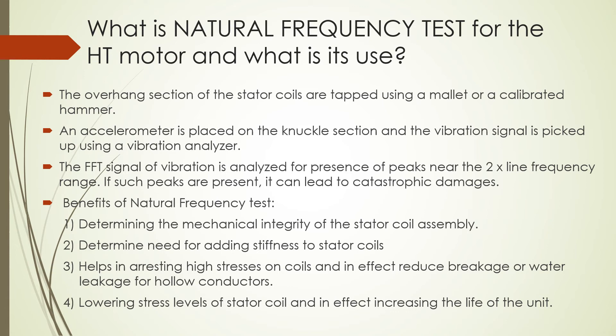The eighth question: what is the natural frequency test for an HT motor and what is its use? The overhang section of the stator coil is tapped using a mallet or calibrated hammer. An accelerometer is placed on the knuckle section and the vibration signal is picked up using a vibration analyzer. The FFT signal of vibration is analyzed for presence of peaks near two times the line frequency range. If such peaks are present, it can lead to catastrophic damage. Benefits include: determining the mechanical integrity of the stator coil assembly, determining the need for adding stiffness to stator coils, arresting high stresses on coils, reducing breakage or water leakage for hollow conductors, and lowering stress levels to increase the life of the unit.